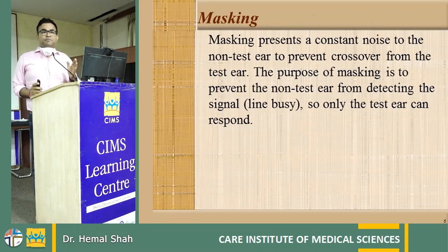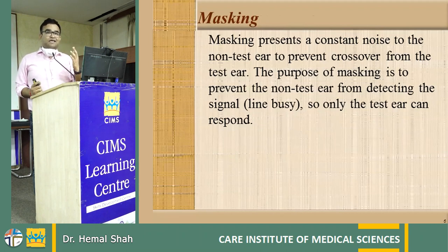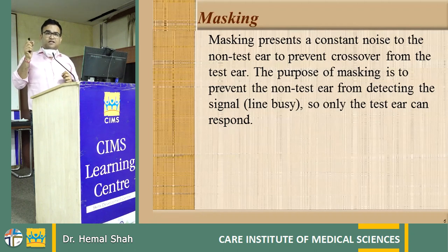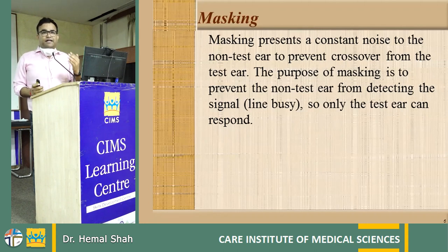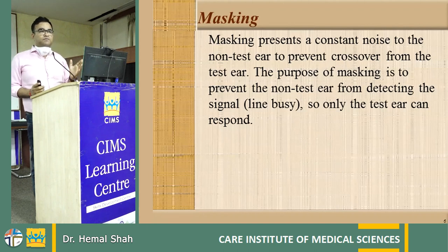The audiometry test is done separately for the right ear and the left ear. Whenever you are testing the right ear, there is always a possibility that the patient is responding falsely because they can hear from the left ear. To mask the left ear, we give a certain intensity of sound to the left ear so that we can exclusively get the data of the right ear only. This is known as masking — it represents a constant noise delivered to the non-test ear to prevent crossover from the test ear.